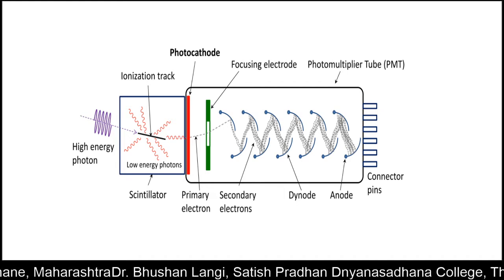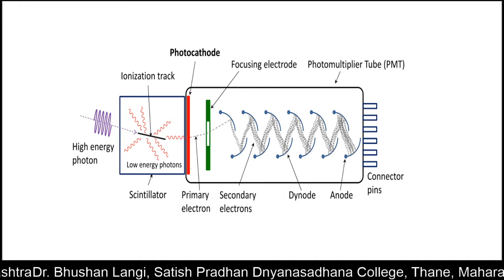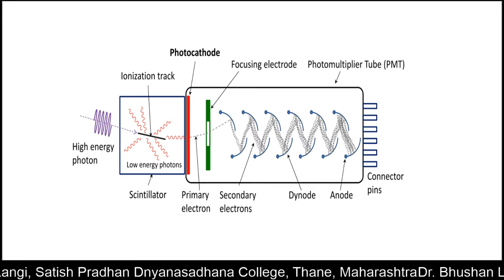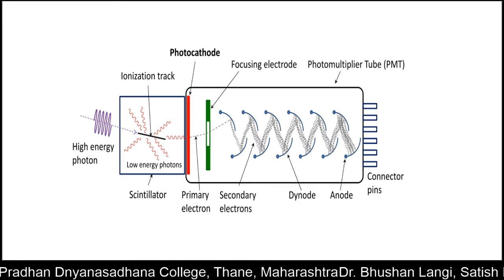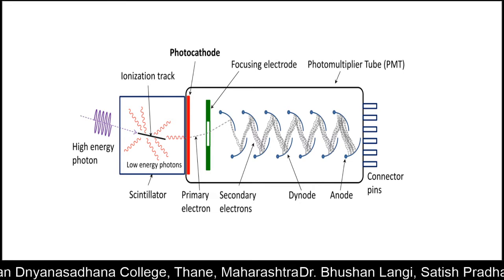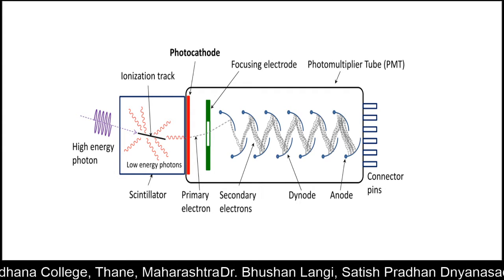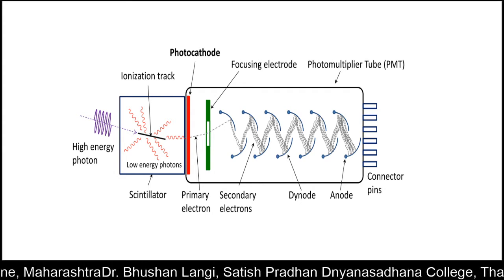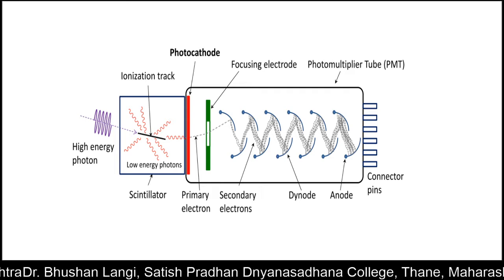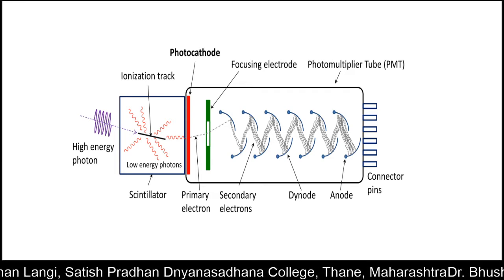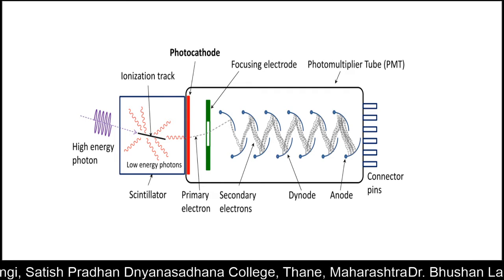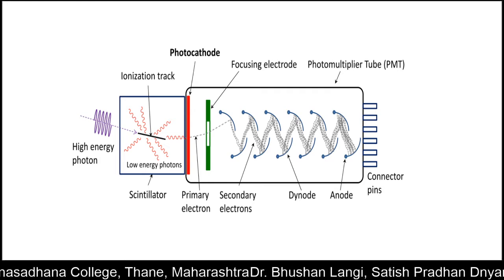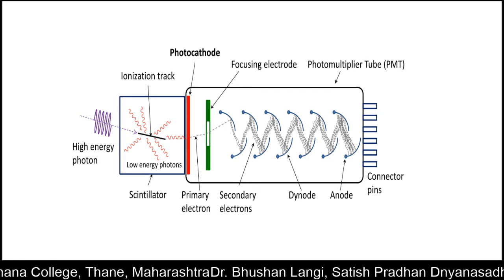The photomultiplier tube has a series of electrodes known as dynodes. This series of electrodes is arranged with increasing potential. When a primary electron is incident on the first electrode, that one electron produces 10 secondary electrons.